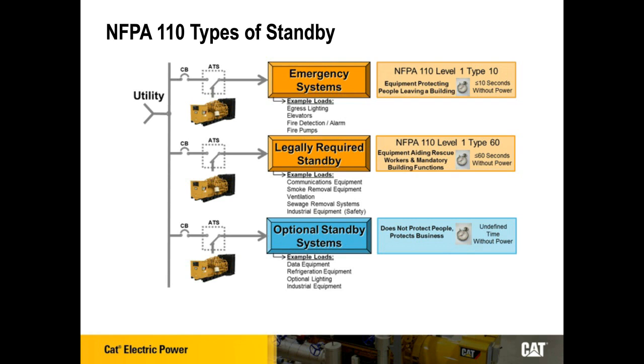In the middle, we have legally required standby, or NFPA 110 level 1 type 60. These are loads that are important for rescue workers or things that must happen in a building, such as sewage pumps or ventilation. These loads are allowed to be without power for up to 60 seconds after the utility power goes away.